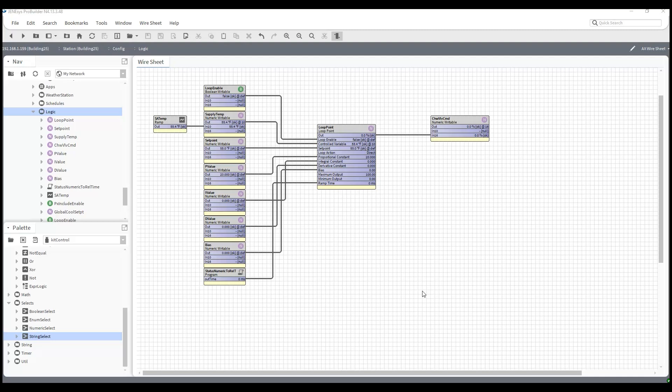So we're going to talk about the loop point. The loop point is what we use to either control other modulating outputs such as valves, dampers, VFDs, or we can actually use it to stage digital equipment, like multiple compressors or boilers. The way I see a loop point is effectively cruise control in a vehicle. You're driving on a highway and you want to maintain a speed, so we set the cruise control and the car will accelerate and decelerate to maintain that set speed. That's what we do here with the loop point.